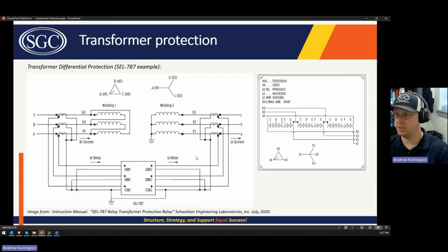We could also look at the winding connections and see that the polarity of H1 is connected to the non-polarity of H2, which is a DAB transformer. So again, that would be the Y winding has a 30-degree lag to the delta winding.